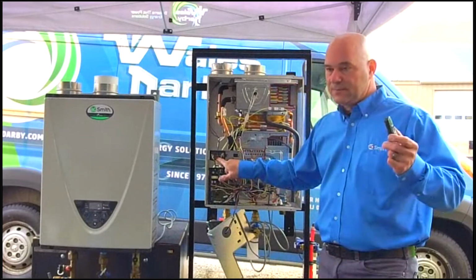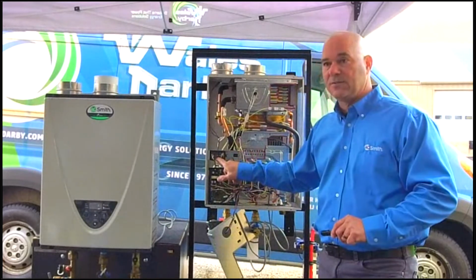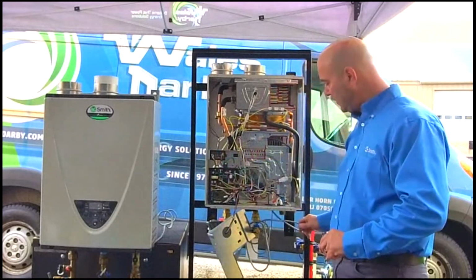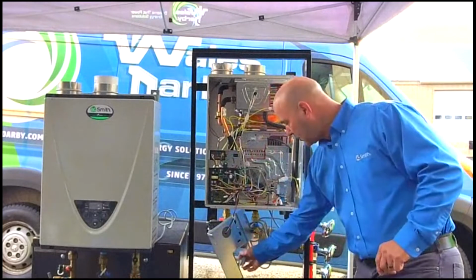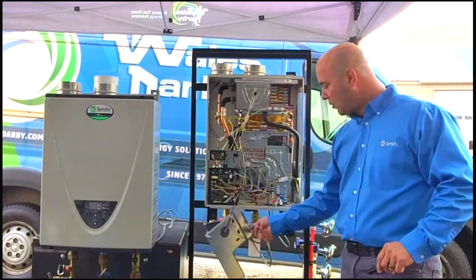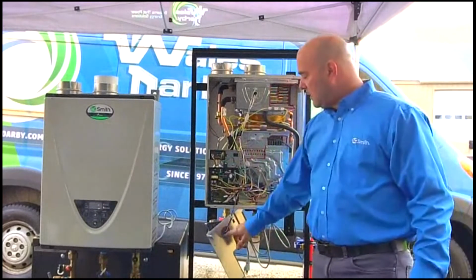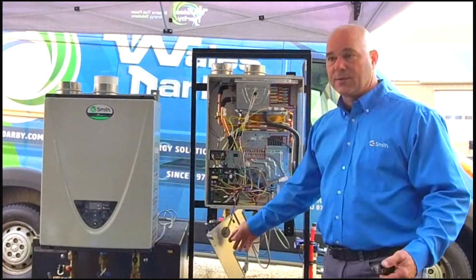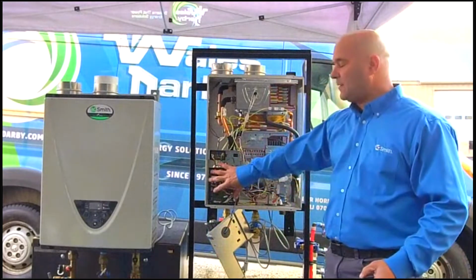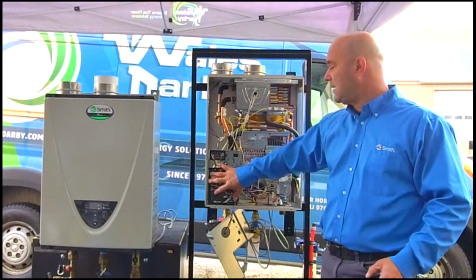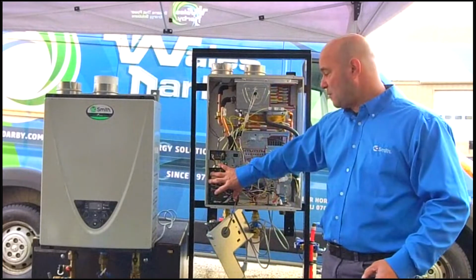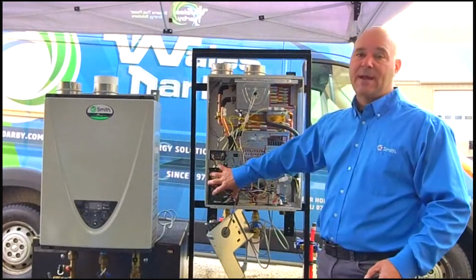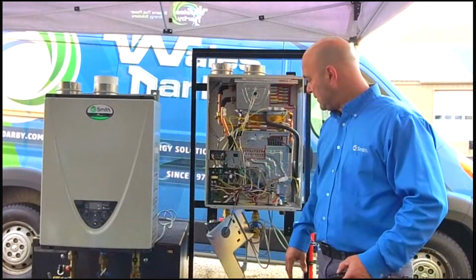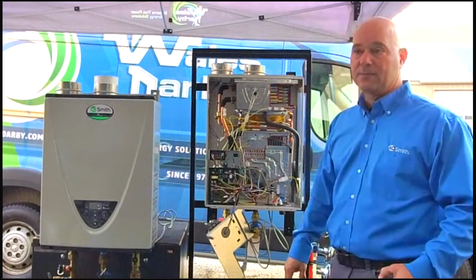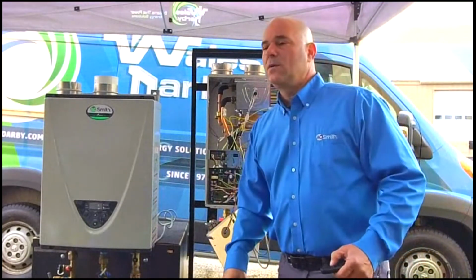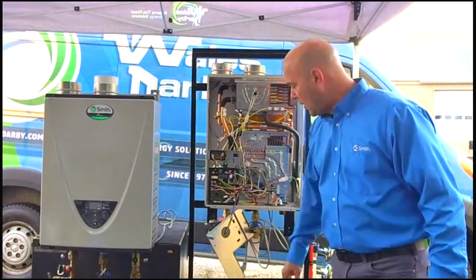We also have a surge protector built in. So this will protect you. You know, these are 115 volt units, but it'll protect you much further out than 115 volts. They come with a plug, you know, typical appliance type cord, 3-prong appliance cord. So that's nice. And the controller, you know, is easily removable. You're not going to do a whole lot in this box. And we just don't see a lot of issues with this control. I'm working on these things 9 years now. I've replaced one of these in 9 years. So pretty robust. I haven't seen a lot of failure there. So again, we'll protect you. Now back to the control.